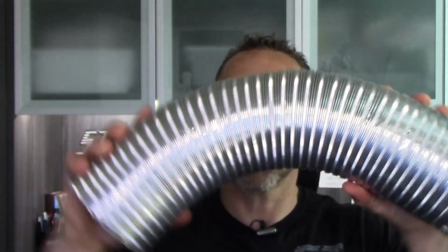It can be made out of corrugated stuff. It could be this flexible foil stuff. It could be this semi-rigid flexible foil stuff. There's a bunch of different materials that can make up the dryer transition duct. You can have up to 8 feet of that material, and it can be flexible. It needs to be UL listed. There's a special listing. I'm not going to get into all the details, but there's a UL listing that it needs to have.